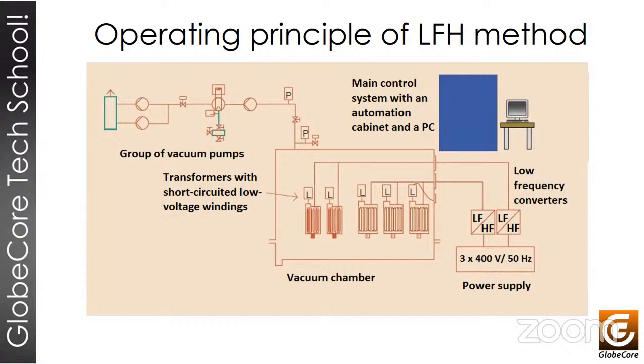In order to continuously monitor currents, voltages, resistances, and vacuum level, this system uses unique control and monitoring arrangements. The system determines the temperatures of high voltage and low voltage windings with high precision and allows heating the high voltage windings independently if the temperature thereof is lower than the temperature of the low voltage windings.